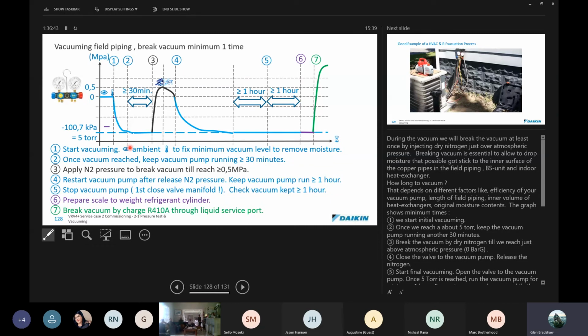Moisture that's in the system as a liquid is another problem. This will often hamper a vacuum, and if we suspect that there's that type of moisture in a system, you may have to start cutting pipes open and blowing through to find out where it is.